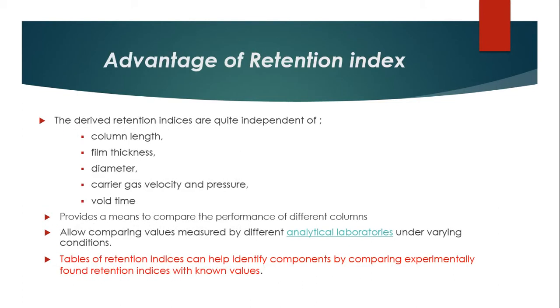An advantage of the retention index is that derived retention indices are quite independent of column length, film thickness, diameter, carrier gas velocity and pressure, and void time. This provides a means to compare the performance of different columns and allows comparing values measured by different analytical laboratories under varying conditions. Tables of retention indices can help identify components by comparing experimentally found retention indices with known values.